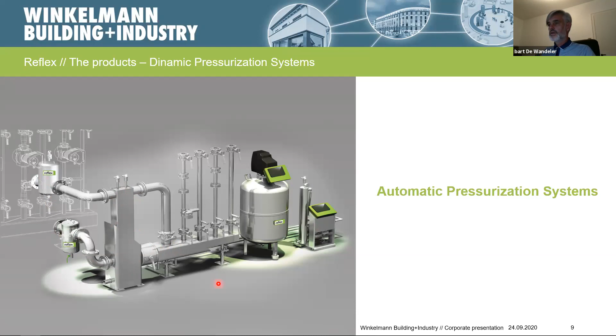If we see today what the advantage is if we use, for example, a pump or a pressurization system with compressor, first of all we can reduce a lot of space and a lot of expansion vessels, because a static vessel is calculated completely differently. A good, healthy static vessel may contain at most 1/3 water capacity, and 2/3 of the vessel is actually only air. So when we look at the bigger systems, providing 8 or 10 big static vessels is not so common anymore.